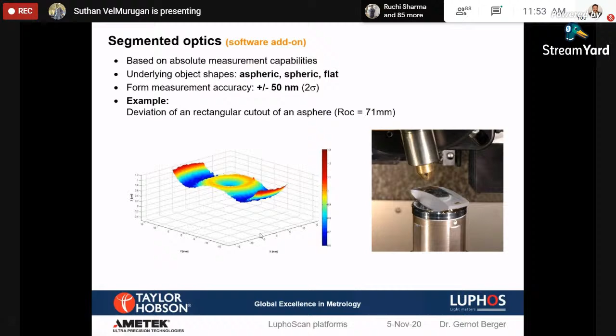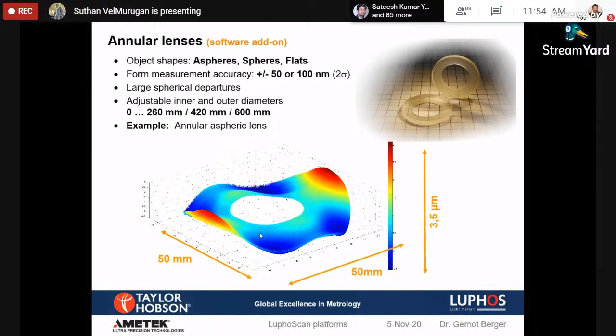So the annular lenses have few limitations on the contact profiler because it has got a hole in the middle, and the thickness of the sample is very less. It's like 1 millimeter, 2 millimeter. It's like very filmy. So we always have, because the contact is going to touch, we should have a proper vacuum check kind of thing. But in non-contact, nothing is going to touch, so there is no force acting on the sample. So it is always preferable for the filmy sample on the non-contact principle.